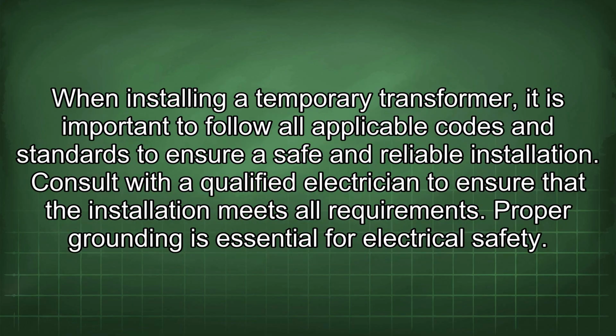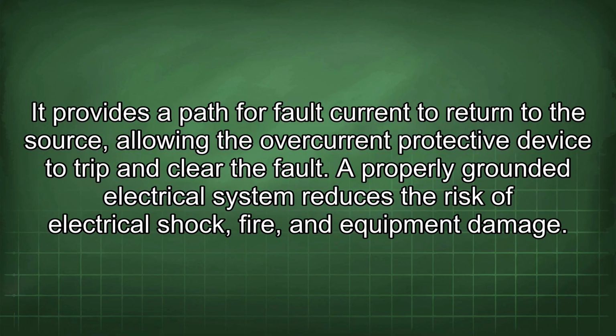When installing a temporary transformer, it is important to follow all applicable codes and standards to ensure a safe and reliable installation. Consult with a qualified electrician to ensure that the installation meets all requirements. Proper grounding is essential for electrical safety. It provides a path for fault current to return to the source, allowing the overcurrent protective device to trip and clear the fault. A properly grounded electrical system reduces the risk of electrical shock, fire, and equipment damage.